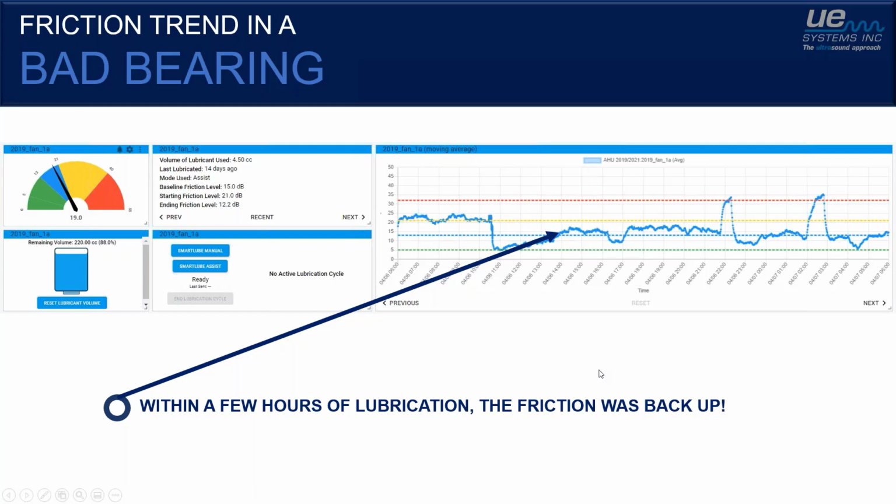Grease can fill up some small divots and things like that in the bearing, but eventually it's going to wear off and we're going to see that friction. This is exactly what happened in this use case. So if I was to go back to this slide and say, hey, everything was good, the reality is no, we need to monitor this not only before, but also after.